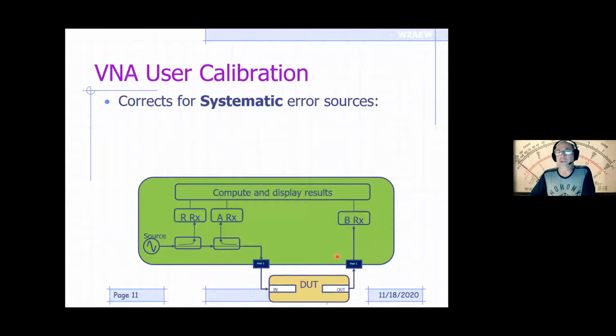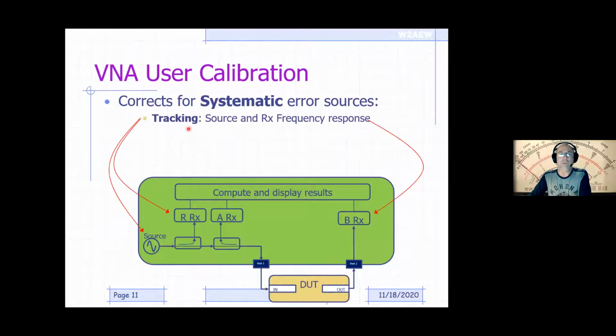So again, the user calibration corrects for what we call these systematic error sources. So things like tracking error. Tracking error refers to the source and receiver frequency response. So the frequency response of the source, of these couplers, of the receivers and things like that, they're going to have their own little bit of frequency response. So part of the calibration measures that, and therefore can remove it from the measurements themselves.